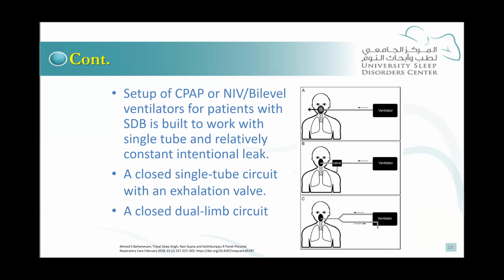You can do a closed dual limb circuit with one inspiratory limb and one expiratory limb. And if a non-vented mask is used in an open single limb circuit, an additional exhalation valve must be added to the circuit to allow CO2 removal. Clinicians and respiratory therapists must be aware of this important difference between ventilators, because the use of a non-vented mask in an open single tube system without an exhalation port in the system can be disastrous.